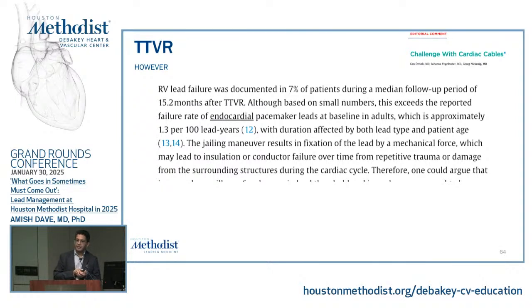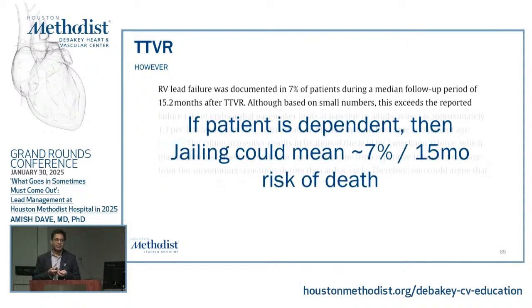The editorial in the same issue raised some concerns, though, about all this, and really a failure rate of 2 out of 28, about a 7% failure rate in 15 months, is much higher than the failure rate of the most horrible recalled lead that we have. It's a significant concern, and this is really the important point. If a patient is pacemaker dependent on that lead, a failure rate of 7% in 15 months is really not acceptable. That failure will lead to death at a fairly high rate.